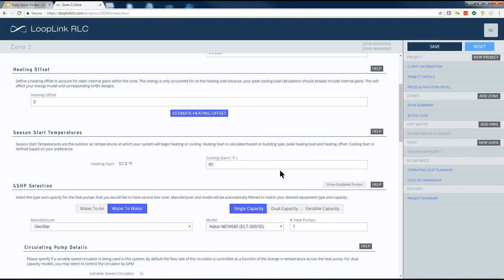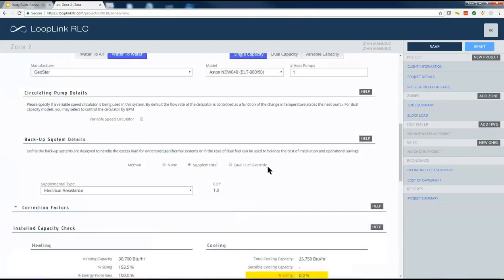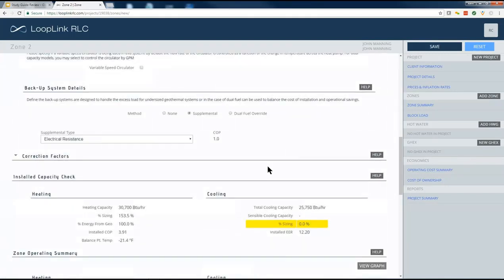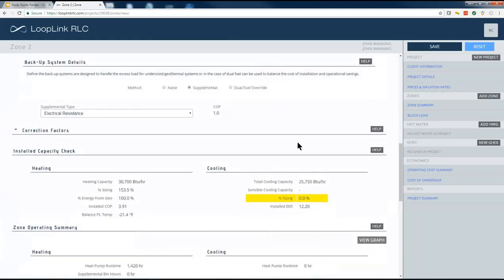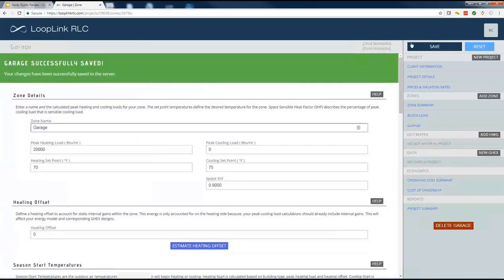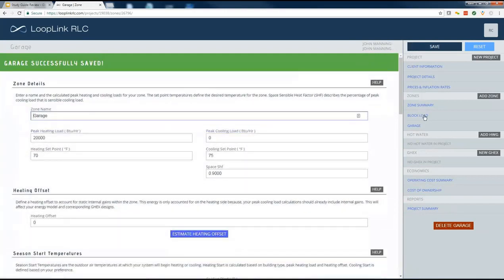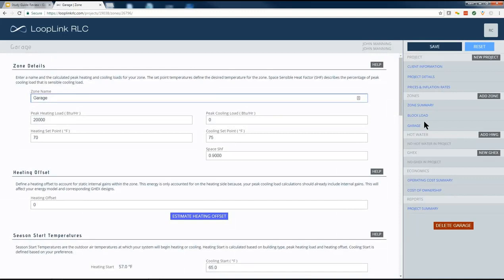So now, skipping over all these other details, because you guys get an idea of how to interpret the page and what's going on, I just wanted to go ahead and save a second heat pump onto this project, make it a little more interesting when it comes time to design the ground loop. So let's go ahead and save that. Now notice I've got two zones. I've got a block load for that forced air system in the house, and then I've got the garage zone, which is the radiant water-to-water system that we've just added, heat-only zone.